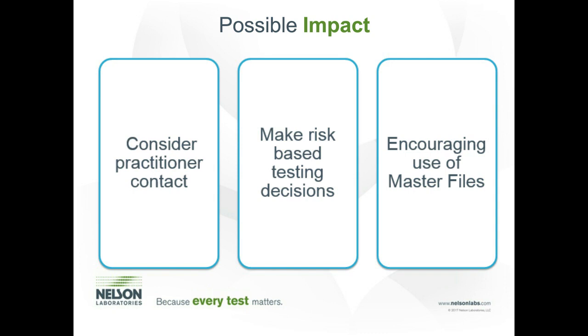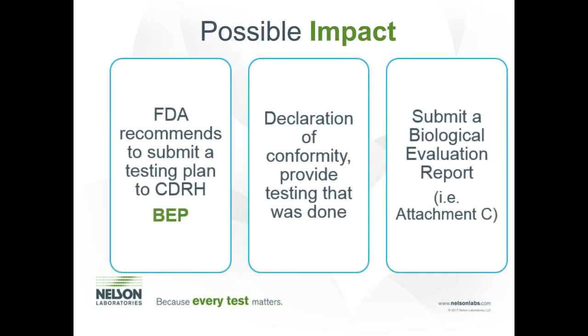They do like to use master files if they're done appropriately. We've seen a big impact from that BEP, the FDA asking us to submit those plans before just checkboxing the testing. Also, they're asking for a biological evaluation report. They even have their own attachment in their document, Attachment C. That doesn't mean you have to do their exact Attachment C, but you should look at what information they're asking for you to provide and then make sure that information is provided to the FDA.